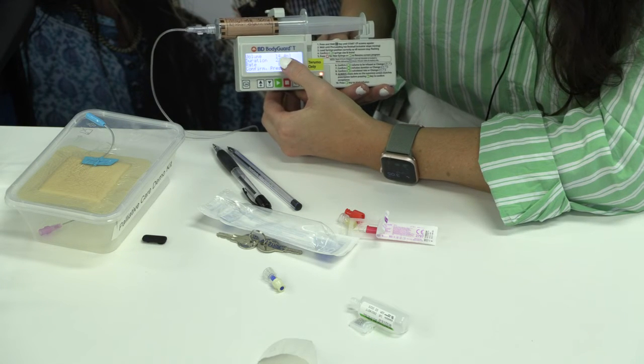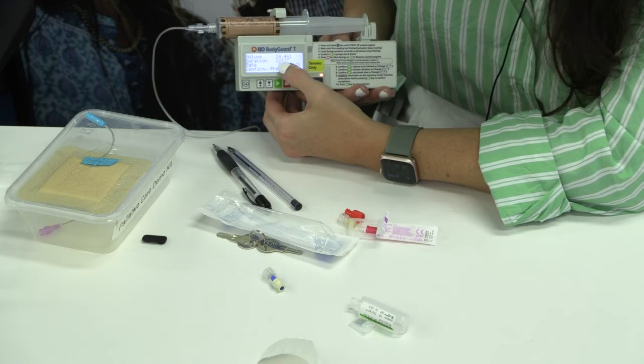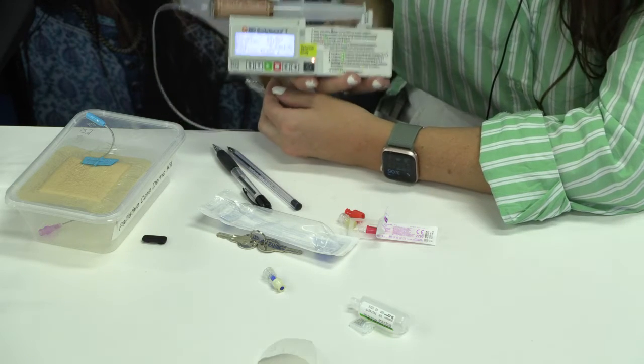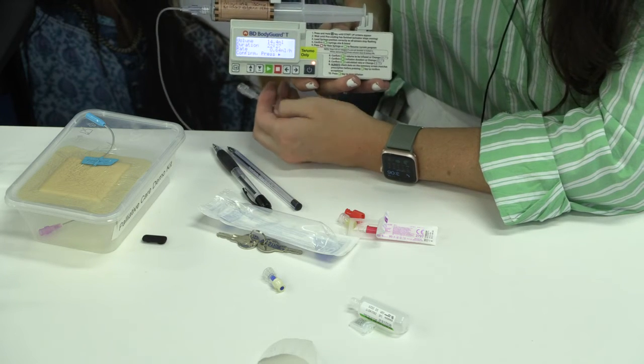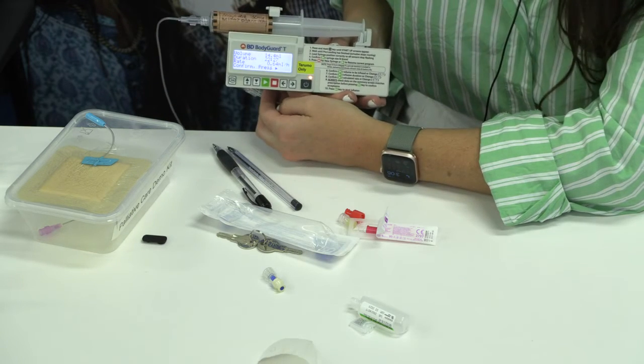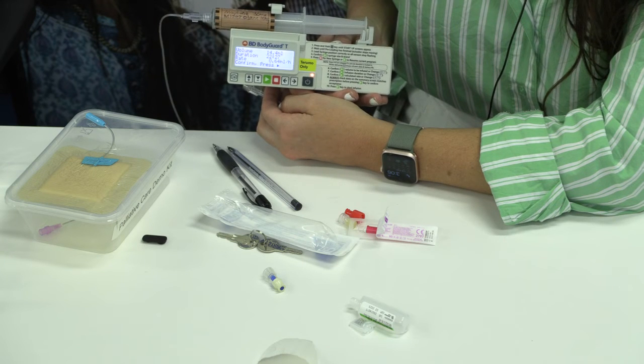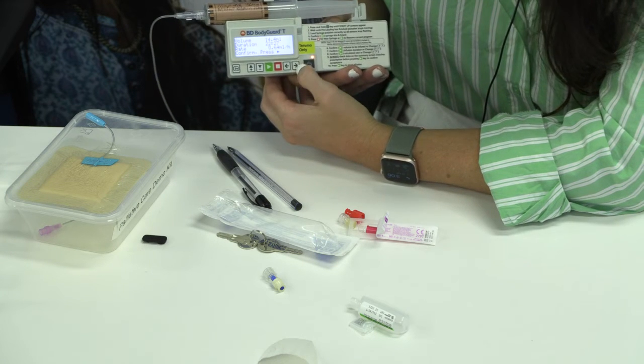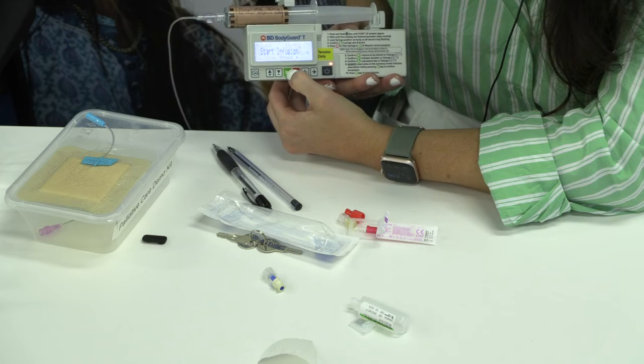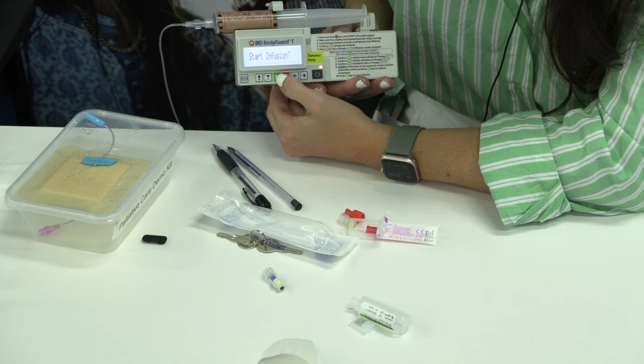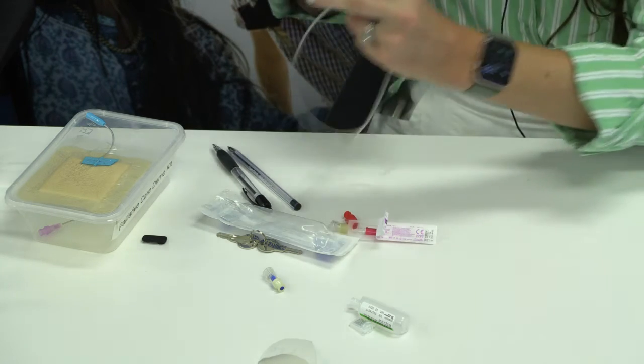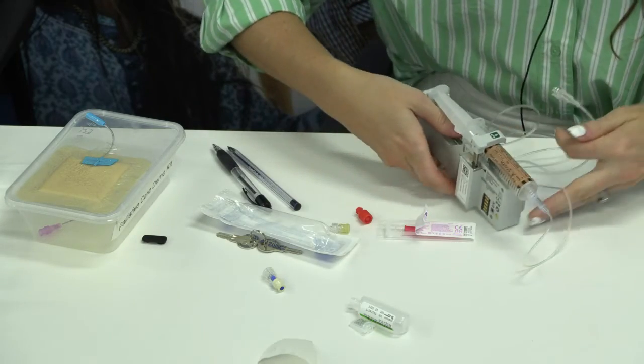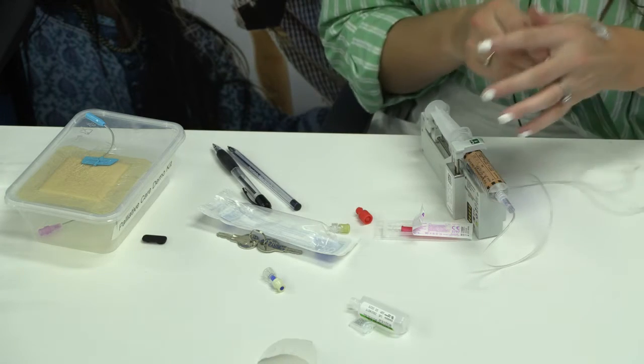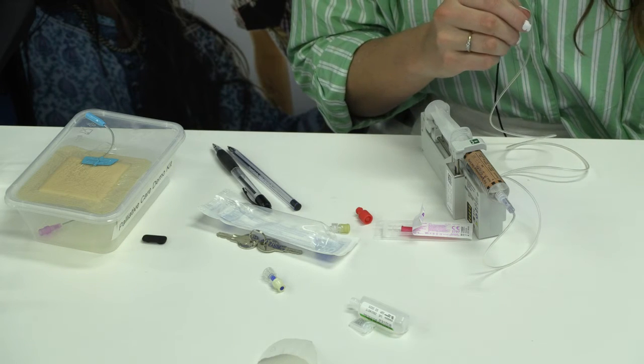Then we'll see that we've now got 14.4 mils and a reduced duration, which is again expected for that initial running of the pump. But the rate has stayed the same, so that means they're going to get the accurate dose. We then press to confirm. We've now gone to the patient. Sometimes we can do all of that. We then come to the patient. Again, all the instructions are on the screen as well.